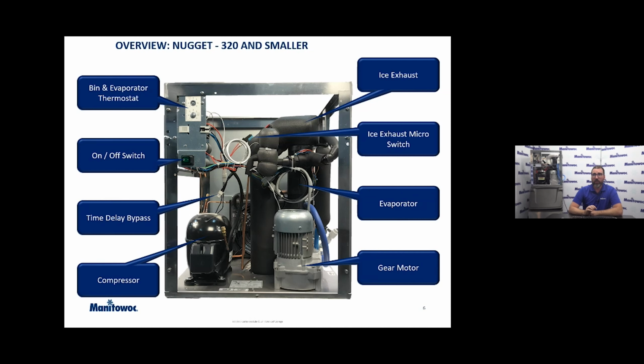You can see our bin level and evaporator thermostats in the top left-hand corner there, that on-off switch that I talked about. A time delay bypass, we'll get into what that time delay means in a little bit. We have our compressor and evaporator over on the right side with the exhaust or discharge, as I like to call it. The micro switch, that's gonna tell us if that ice starts to back up into the evaporator. We know that we're full.